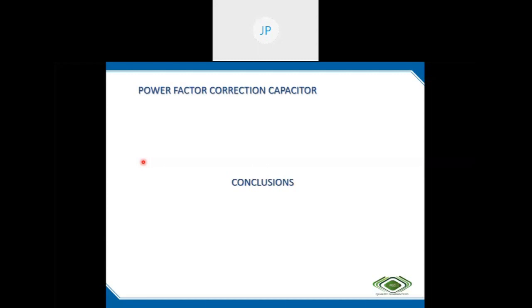If we need real-time compensation for dynamically changing loads, we can use thyristor switched automatic power factor control. Where we need smooth variation of compensation, capacitive and inductive both, we have to go for advanced solutions like synchronous condenser, static var compensation (SVC), or STATCOM. These can be used to control smoothly, in steps as fine as 0.1 kVAr. Normal banks only switch step by step, with no smooth variation available. Due to time constraint, we are not going into that topic.